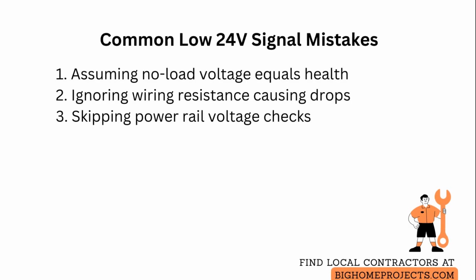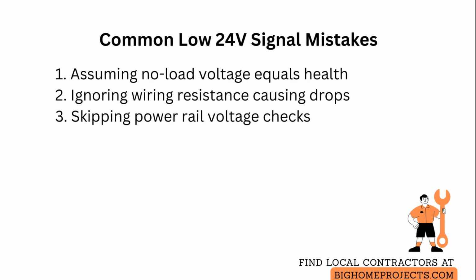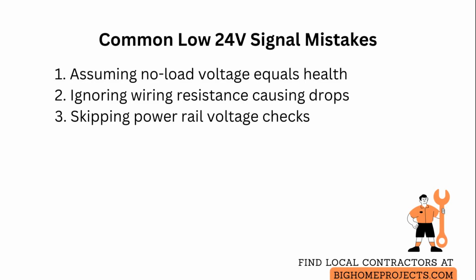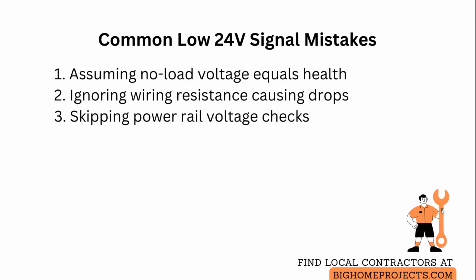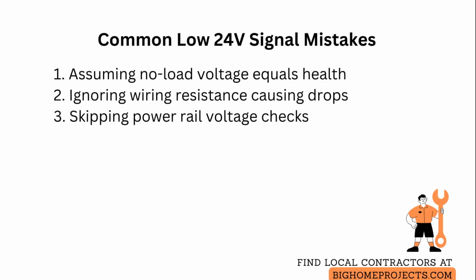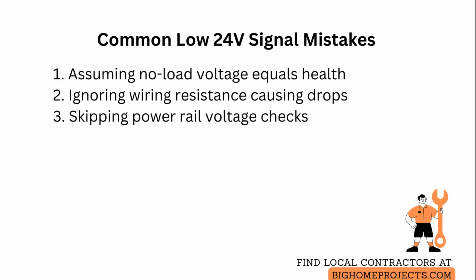Another is overlooking wiring resistance from long runs or thin conductors, which creates voltage drop. Remedy this by upsizing conductors and shortening runs or relocating transformers closer to the load.